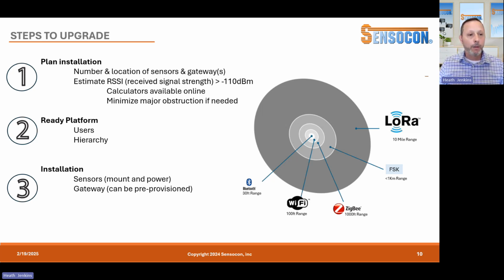So how do you install this? You find out the number, location, and type of sensors, and where you'd want the gateway. You just have to know the gateway needs to be within range of those sensors, and you'll find out whether it's in range quickly because you'll have a received signal strength indication. That needs to be a higher number, for example negative 100 is higher than negative 110, so it just needs to be higher than negative 110 in general to avoid packet loss and interference.